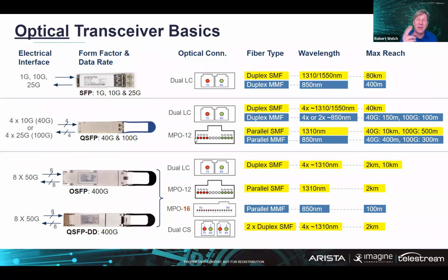You'll hear these things called type A, B, and C for the MTP12 or MPO12 connectors. There's a polarity. If you remember back in the RS-232, 422 days, you had transmit and receive, just like right here with the LCs. Well, you have this law of odd numbers when you patch your MPOs together. You need to flip, and then flip again. Can you do it with the MPO12 connectors? Yes, but you have this odd thing because you want to keep your pigtails type B at the end on each one. So if you go B, B, and B, you'll be okay. But remember, that's 12 fibers but really 8 fibers in use, and you want to make sure you get your polarity right. We see a lot of people trying to save money from a fiber plant perspective, and they end up going with something that puts them on a pair of fibers, because you can easily change that polarity.